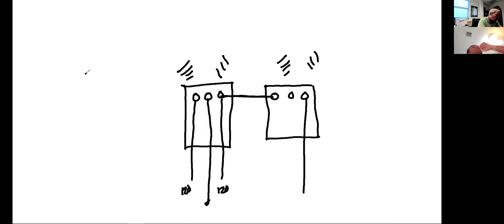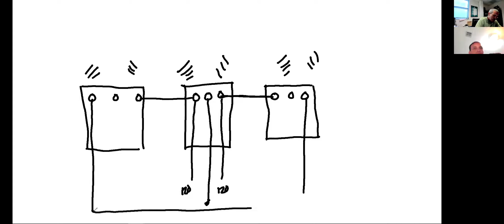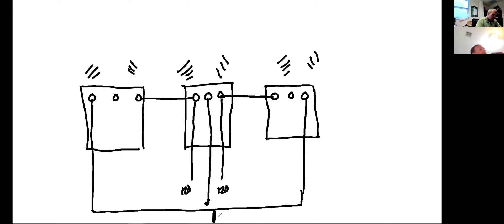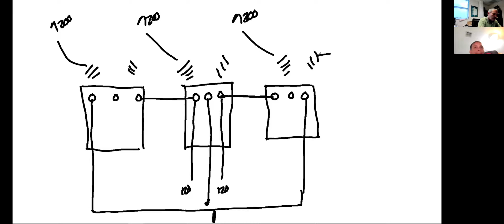As far as a closed delta bank, what do I need to add? How many transformers do I need? 3. So I need another transformer: 1, 2, 3. And draw it down like this. All right, I'm going to have a tie-in bus between the two. This direction now, I've added my third. Both this wire and this wire interconnect and make one conductor. Suddenly, I have just created a closed delta bank.